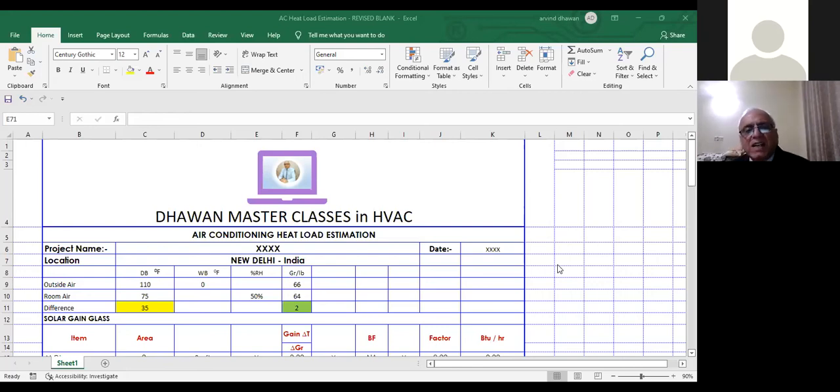So standard design is taken as bypass factor as 0.1. We assume 90% of the air will come into contact for heat transfer, and about 10% will not come into contact for heat transfer. So if it's for normal comfort applications, we take it as 10%. Now, suppose you have a special application, very low dew point and all the factors involved, then the bypass factor is specially designed by the coil manufacturers to make it less than 0.1. Normally, for normal comfort air conditioning, the fins per inch, the size of tube, and all these things are designed for a standard application as 0.1.